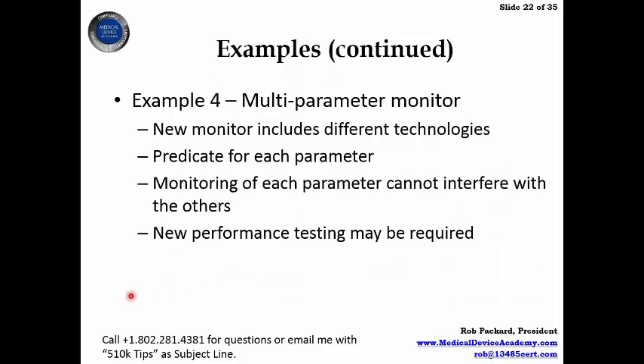Here's another example. Example 4 talks about multi-parameter monitors. At one time, they didn't have multi-parameter monitors. They only had monitors. So when somebody came up with the idea of combining two monitors, you have two different predicates. One does temperature, the other one does blood pressure, and now Welch Allyn comes up with this new multi-parameter monitor that does both temperature and blood pressure. So you might have to show some new performance testing data, but you're going to show it's the same intended use as each of the two predicate devices and the same technological characteristics. But there are exceptions out there. If somebody comes up with a new infrared temperature measurement instead of an RTD sensor, that's going to be different technological characteristics, and you're going to have to show that the risks associated with the new technology are not worse. Primarily, you're going to focus on accuracy and precision of the device and making sure it can't shock somebody or hurt somebody.